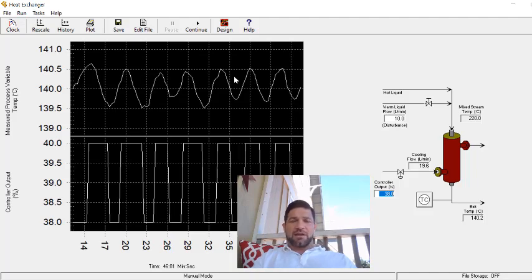So increase the gain by about ten percent. Increase the derivative by about ten percent. And see how that affects the controller response. And make changes until you're happy with the response.